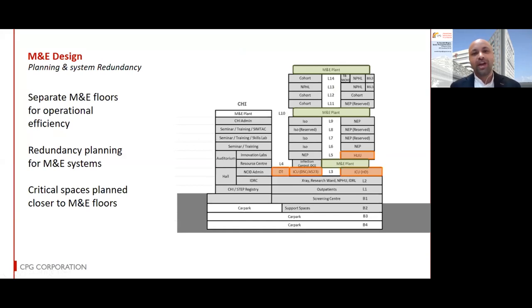Traditionally, we plan for AHUs adjacent to the space it caters to. Here we have an example of how M&E can be consolidated on separate floors to improve operational efficiency. This eliminates disturbance to the patient areas during maintenance, and M&E floors can be located closer to the key functional units like ICUs, OTs, etc., to service high MEP demand. This strategy also allows the flexibility to plan for system redundancy, where co-located AHUs can be shared for use during downtime and maintenance.